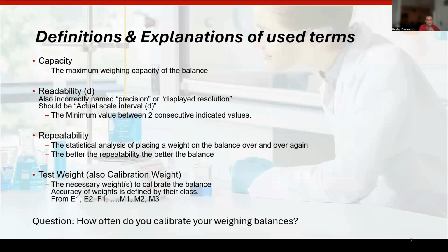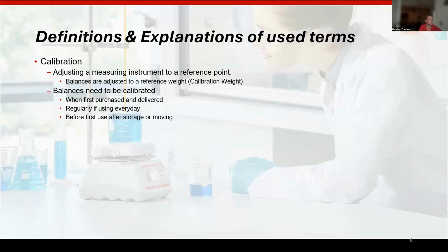But with the portable balances, what you should be doing is recalibrating every time it's moved, so when it's inside a cupboard and then you pop it out for the lessons, it should be recalibrated then, because each time it's moved, it is essentially outside of calibration. But with normal laboratory weighing balances, you can get away with doing it once a year if it's regulated, but we'll go a bit more through the calibration later on in a couple more slides.